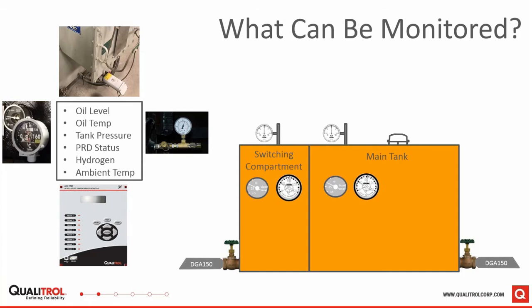We can also monitor the pressure in the tank. Typically you like to keep positive nitrogen pressure on these transformers so that in cold weather, the oil level doesn't go low and draw a vacuum. And so pressure is another thing we can easily monitor. If it's got an existing pressure gauge, you can put that pressure gauge on a T and install a pressure transducer coming back into a 509 or a QTMS. The picture on the right side of the box shows an installation of a pressure gauge with a pressure transducer.